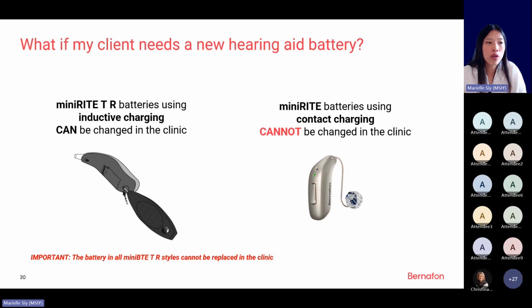So replacing the batteries depends also on the style and the type of charging that the hearing aid uses. So for the miniRITE TR batteries with inductive charging, the battery can be replaced in the clinic by you, the hearing care professional. So as you can see in this picture, the battery door can be opened using this tool. And then you may want to make sure that the client is aware that if or when they hear the battery low warning all the time, even when the day is not finished, then it is recommended that they come to your clinic for a battery health check. Also, please note that the mini BTE TR hearing aids, which also use inductive charging, cannot be replaced in the clinic. And the reason is because the battery of the mini BTE TR is fully encapsulated in the hardware, so you still need to send this to the lab and you cannot change it yourself.